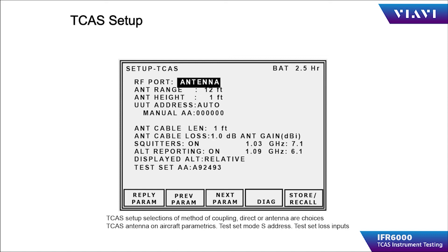Measure and input the distance and height values for the antenna range and height. Select auto for the UUT address so that the IFR 6000 can automatically determine the mode S address of the aircraft being tested. If the test set has trouble determining the address, then the selection should be manual and the operator must input the desired test aircraft address.